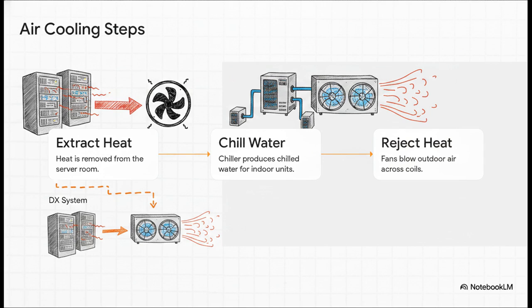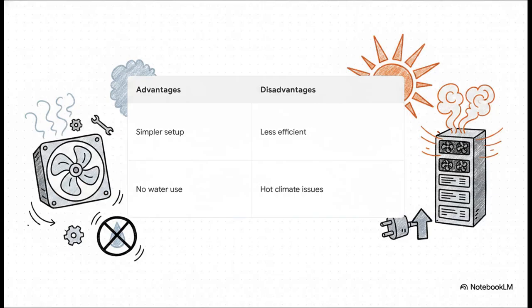But here's the magic mechanism. Instead of using a complex cooling tower outside, large condenser fans just blow outdoor air directly across coils to reject that heat into the atmosphere. Actually, I should also mention that some smaller data centers might bypass the chilled water entirely. They use direct expansion, or DX systems, where a refrigerant just absorbs heat from the room and transfers it straight to an outdoor condenser. Let's weigh the pros and cons here.